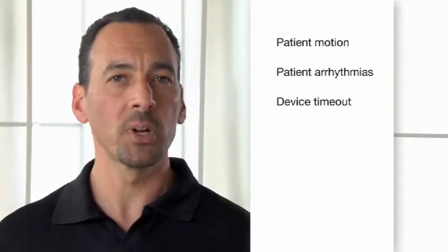Here are some important considerations. Patient motion can prolong the measurement process and may cause discomfort. Be sure the patient's arm is relaxed and that the cuff is not bumping against other objects. Patient arrhythmias can prolong the NIBP measurement time. If the monitor is unable to obtain a reading in 120 seconds, then it automatically deflates the cuff.